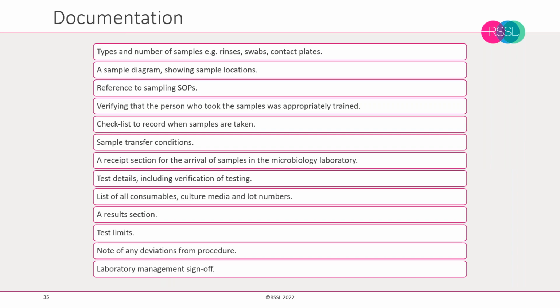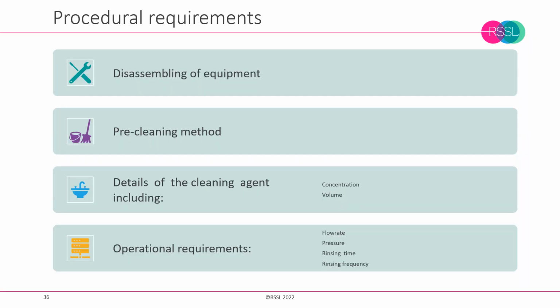As with any form of validation, the cleaning validation should be appropriately documented. On the slide there, for you to read as a takeaway from the webinar, are some of the key criteria that need to be included in the cleaning validation documentation. In particular, the use of checklists is really important, and this can also help in structuring regulatory submissions. It's also important that the SOPs that come out of the cleaning validation, the actual documents that operators are expected to follow, reflect what really goes on in the cleaning validation, so that they cover things like how to disassemble equipment, the right cleaning method to be used, the concentration of the cleaning agents, and controlling things like flow rate, pressure, rinse times, and that people are appropriately controlled against this.